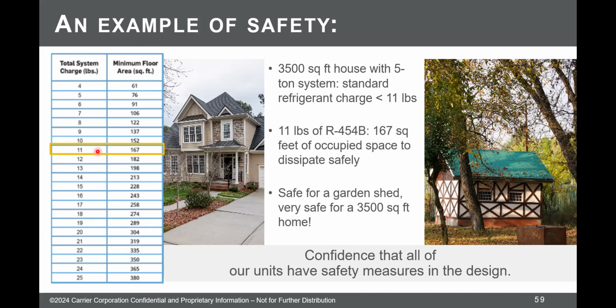So for example, if I have a rooftop or a furnace and I have a leak in the evaporator and refrigerant's leaking out, that leak will go into the duct system and it'll be distributed to all of the rooms that are ducted to that rooftop or furnace. So the whole house, for example, would get all of the leak and it would spread out between all of that. However, if I have a multi-head mini split system or a multi-head VRF system, I might have one evaporator coil sitting in Mrs. Jones's home office, and her home office may be a 10 by 10 room, 100 square feet. If she has 11 pounds of charge in her system and her room is 10 by 10, that's not big enough, right?